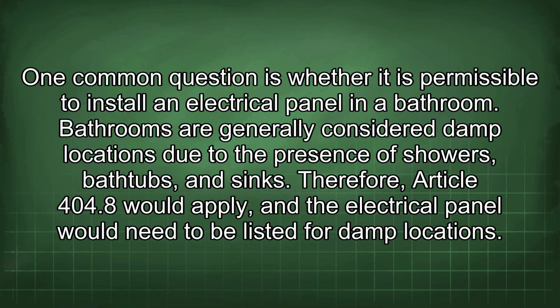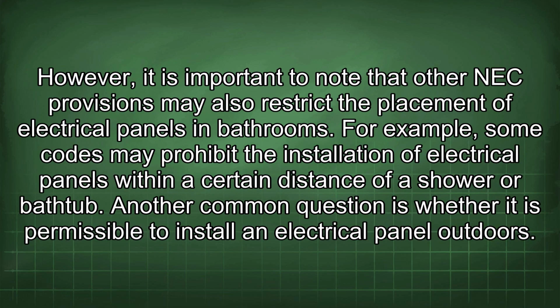One common question is whether it is permissible to install an electrical panel in a bathroom. Bathrooms are generally considered damp locations due to the presence of showers, bathtubs, and sinks. Therefore, Article 404.8 would apply, and the electrical panel would need to be listed for damp locations. However, it is important to note that other NEC provisions may also restrict the placement of electrical panels in bathrooms. For example, some codes may prohibit the installation of electrical panels within a certain distance of a shower or bathtub.